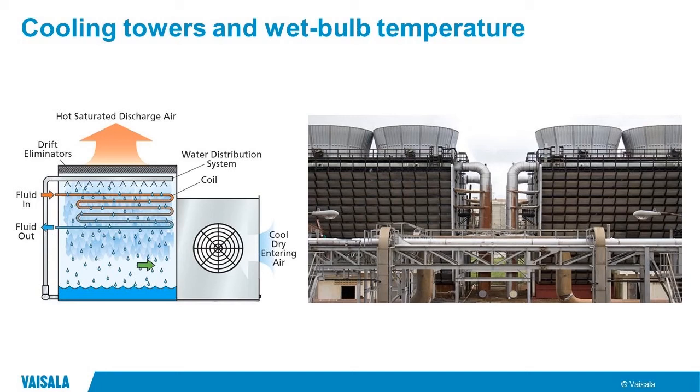Then you have water that's streaming down on these cooling coils, and you have ambient air and some fans blowing this past these cooling coils and the water, so that water is evaporated.